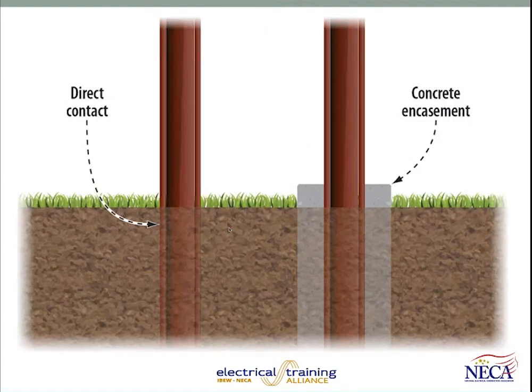And there's a graphic just showing what we mean. The electrode is actually the steel that is in direct contact with the earth for 10 feet or more. And the same thing on the right, where you see steel that is encased in concrete that's in direct contact with the earth for 10 feet or more.